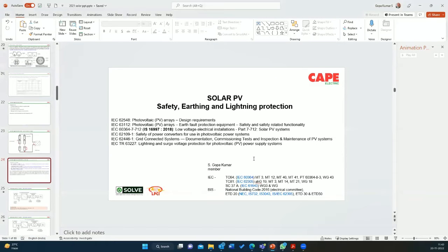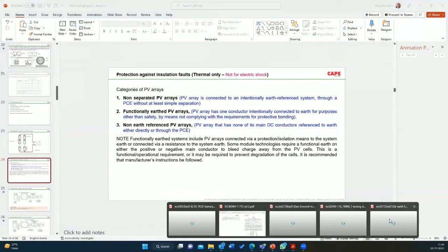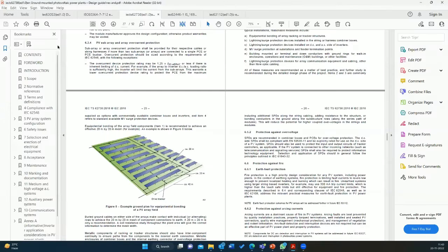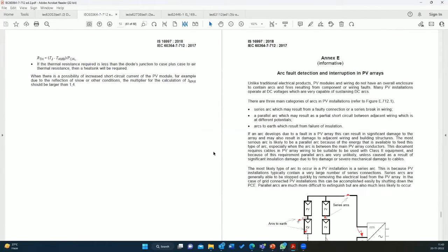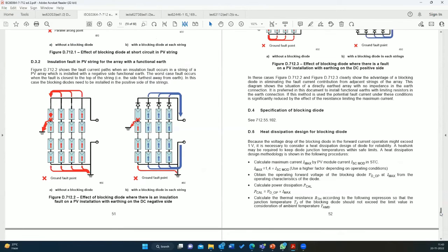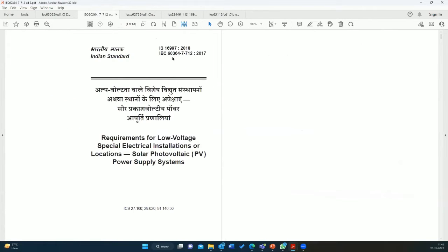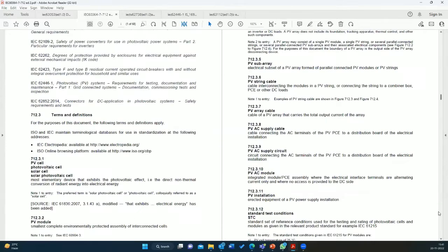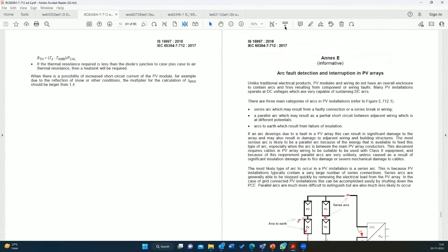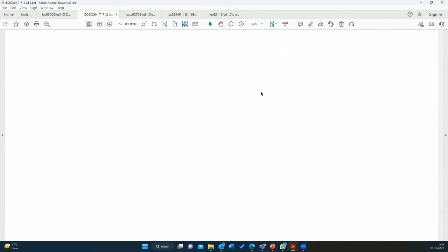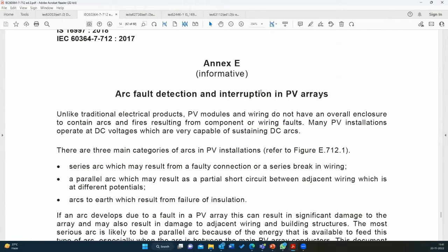Very interesting to read. I'm just showing you the standard. This is an Indian standard, IS 16997, which is IEC 60364-7-712. I go to the annexure just to show you about the dangers of arc, which is, as I said, most important, because fire in solar is a big headache at the moment in the country. Annexure, informative: arc fault detection and interruption of PV arrays.